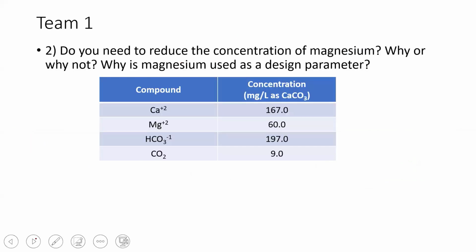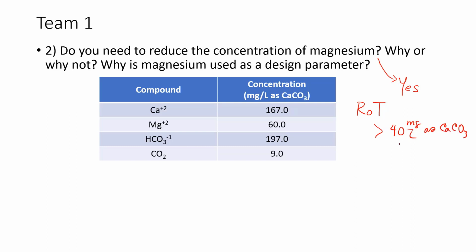The next thing I asked you was, do you need to reduce the concentration of magnesium? And the answer is yes. The reason is the rule of thumb, and you'll see that there's a lot of rules of thumb that we will use in the semester. These are based on experience, that if the magnesium concentration is greater than 40, we want to remove magnesium.